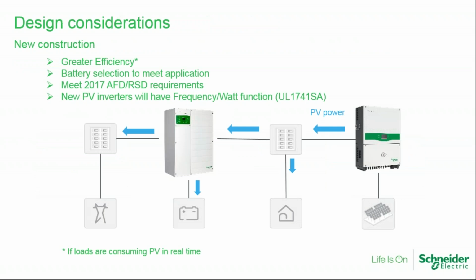Now, one of the things with AC coupling is you get better efficiency because the PV inverter's selling is cheaper, or is basically 98% efficient. You need to make sure that you size and select a battery that's good for the application. A lot of times in AC coupled applications, they want to use the smallest battery bank that they can, and that's not necessarily a good solution.